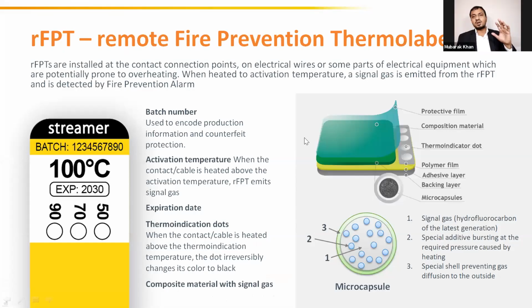So let us talk about the rFPT. RFPDs are installed on the contact connection points on electrical wires or some parts of electrical equipment which are potentially prone to overheating. When heated to activation temperature, a signal gas is emitted from the rFPT and is detected by the fire prevention alarm.